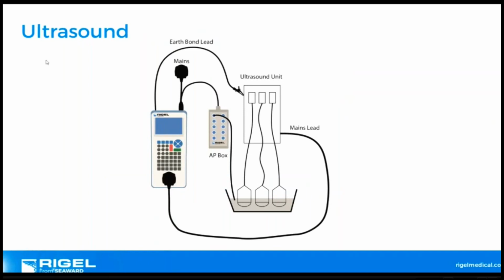And then ultrasound, what we can do is if we immerse all of the probes in this saline solution here, we can put the mains and applied part from one connection, and this at 230 would be 254 volts. Because this lead is immersed from the applied part, this is at mains potential, reference to ground. Because saline is conductive, if I have any cracks or hairline cracks you can't see with a normal eye, and you can't really get a crocodile or alligator clip on, then I'm not going to be able to test efficiently.